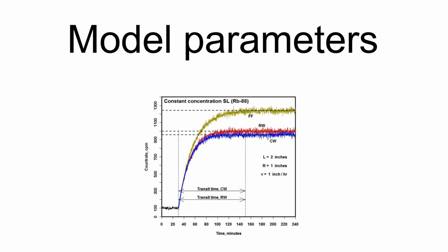Emission abundance refers to the fact that the disintegration of any given nucleus of the isotope of interest in the CPAM analysis may not result in the emission of the radiation being detected, for example a beta particle or gamma ray. Thus, overall there will be some fraction of the disintegrations that emit the radiation of interest, e.g. the 662 keV gamma ray of 137Cs is emitted in about 85% of the disintegrations of 137Cs nuclei.